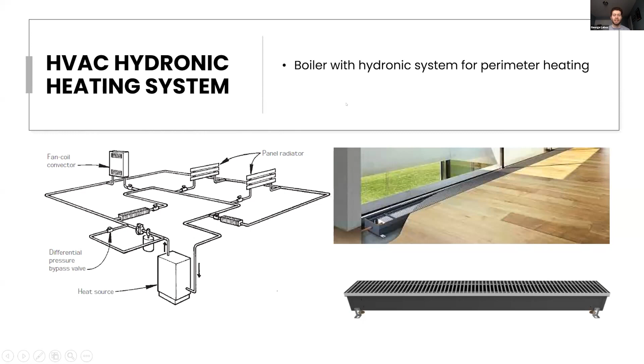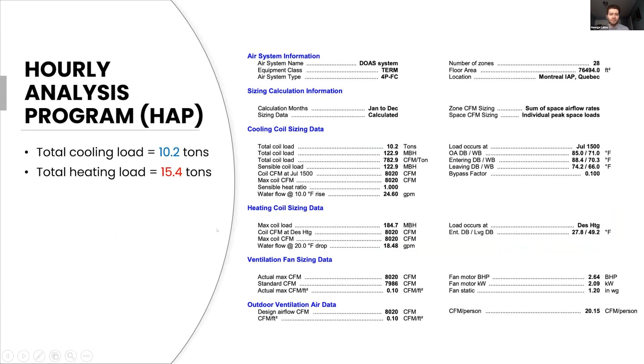Here you can see our hourly analysis program from HAP. Our cooling load came out to 10.2 tons. Our heating load is 184.7 MBH, which is 15.4 tons. And our actual max CFM of outdoor air needed is 8,020 CFM.